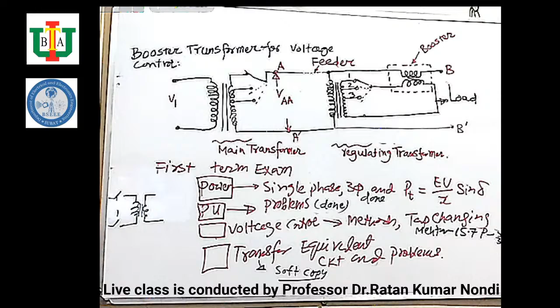In the offload method, in the secondary side, we put a switch. When we want to change the tap, we turn off the switch on the secondary side. The consumer will be without power. That is a disadvantage. That method is not used today, because the consumers will not get power during the tap changing time. Understand? So the offload method is not used.